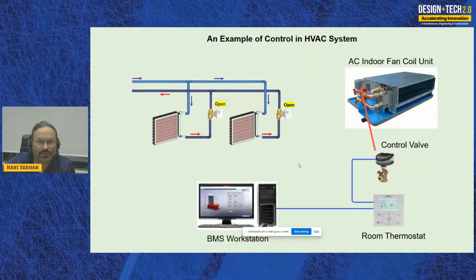So selecting the control valve is one of the important points to be taken into consideration when looking for energy optimization in an HVAC system. Also, modern thermostats are interfaceable with the BMS. Let's say, for example, in hospitals or hotels, if a big group of rooms are unoccupied, it would be so hard to send an attendant to switch off all the AC units. So there's a feature on the BMS that will override the thermostat and can control the whole system, to switch it off or to switch it on from the BMS. So this is another way to achieve energy optimization through the BMS for a smart HVAC system.